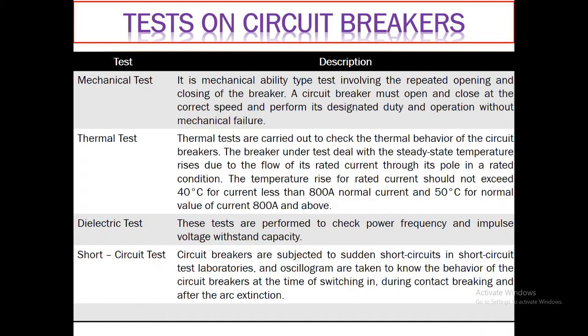Let me give you an example. If during a fault the circuit breaker takes a longer time to open, then it may cause severe damage. And if the circuit breaker is closing at a very fast speed, then it may cause mechanical damage to the circuit breaker contacts. If the speed of closing or opening is more than the prescribed level, then unwanted vibrations may cause mechanical failures of the contacts.